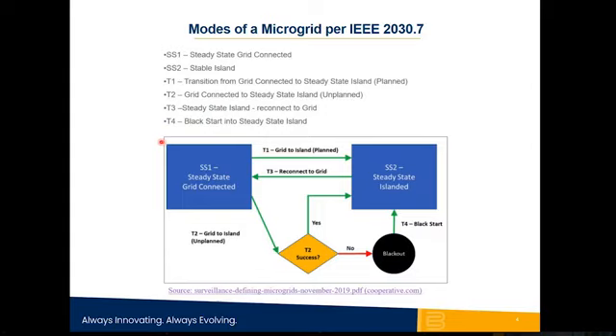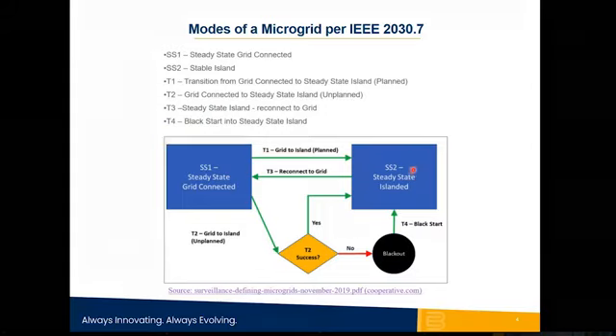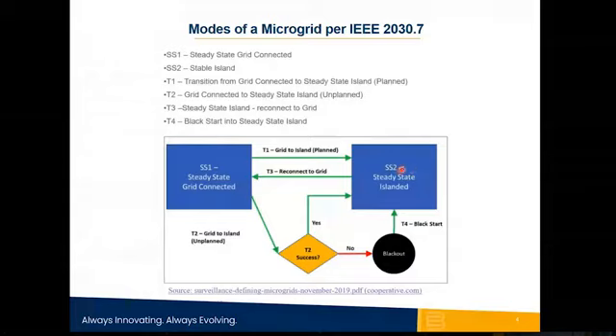You also have a steady state islanded state, where at the point of common coupling, the microgrid is disconnected from the bulk power grid. But then you have several ways of transitioning between these two states. You can have a transition from grid connected to islanded in a planned fashion. So an example of that would be demand response, for instance, where the utility calls up and says, at 10 o'clock this morning, Mr.